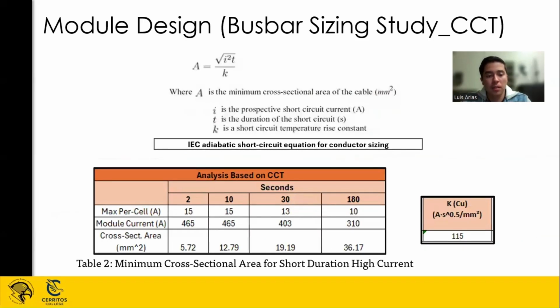To determine the cross-sectional area from the cell calibration table, we look at 2 seconds, 10 seconds, 30 seconds, and 180 seconds. The maximum discharge current is 15 for 2 and 10 seconds, 13 for 30 seconds, and 10 for 180 seconds. We use the IEC adiabatic short circuit equation to calculate the minimum cross-sectional area for each.